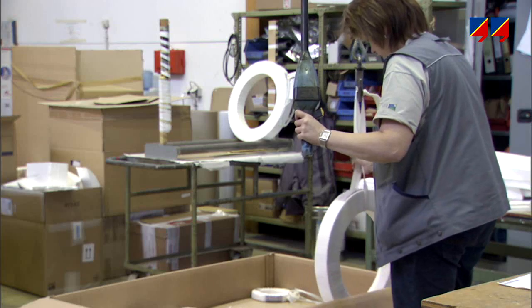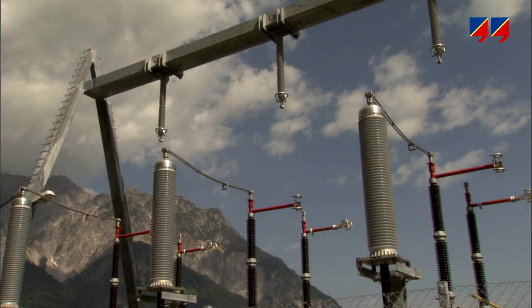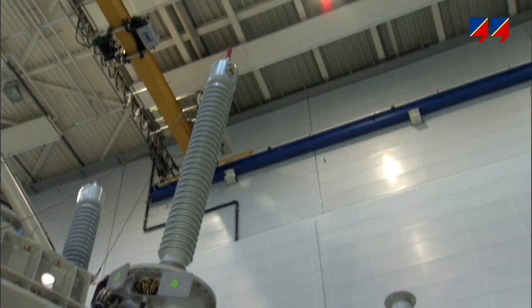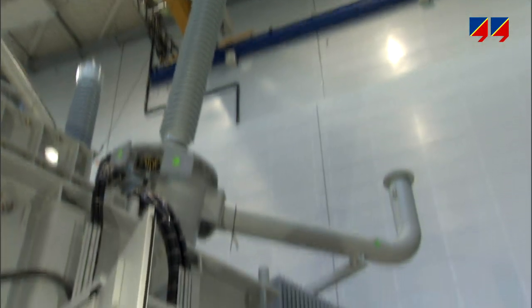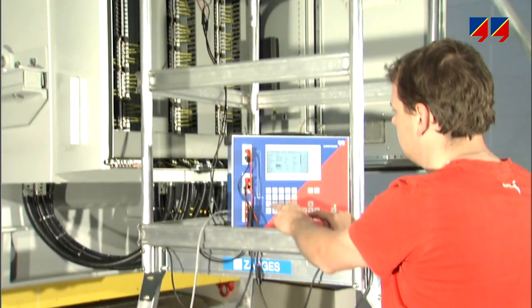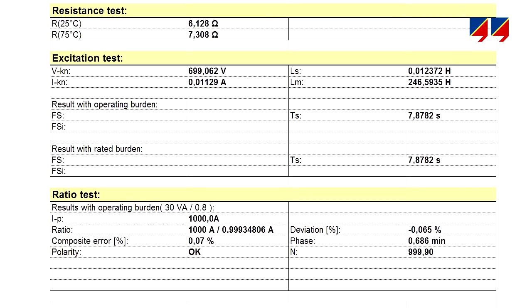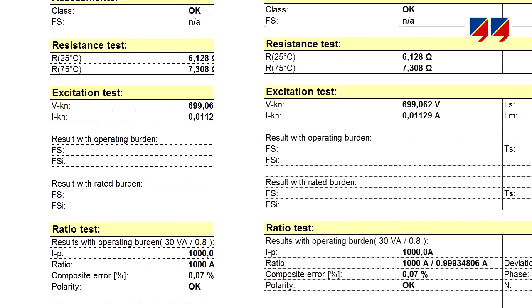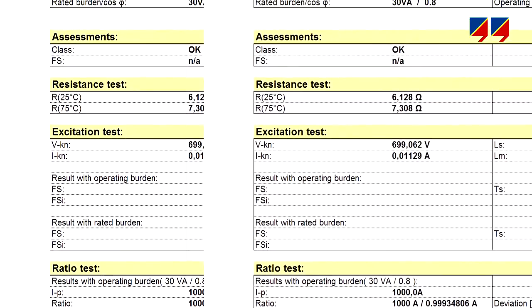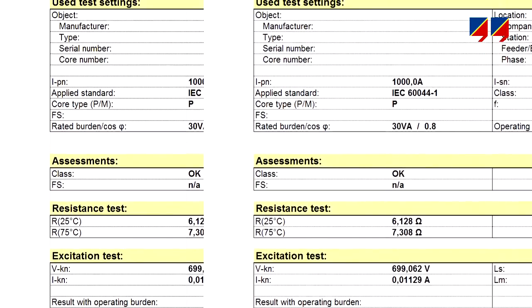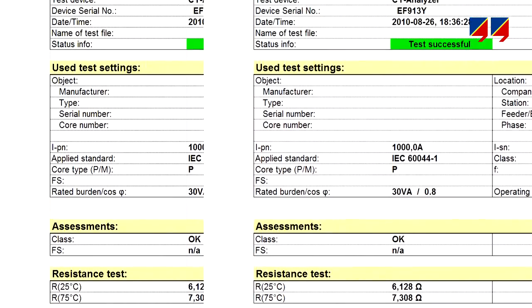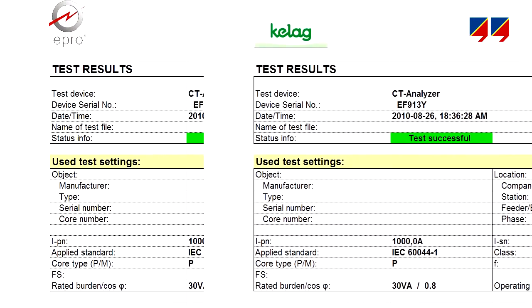In many cases, companies receiving and erecting the CT on site, or installing it into their own high voltage equipment such as a power transformer or GIS, will perform the quality control testing of these CTs with a CT analyzer. The measurements taken before and after shipment can then be directly compared, a benefit for both the manufacturer and his customer.